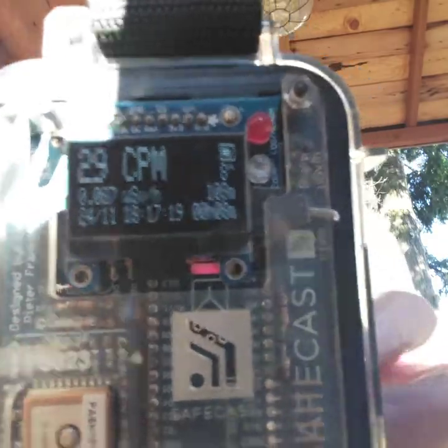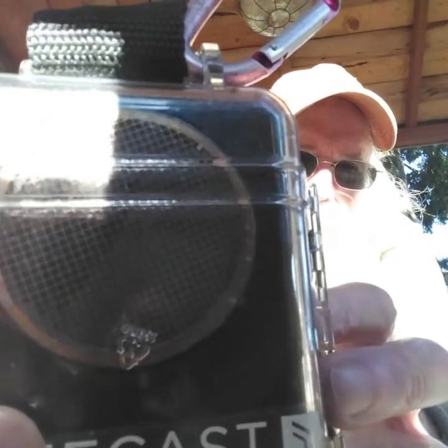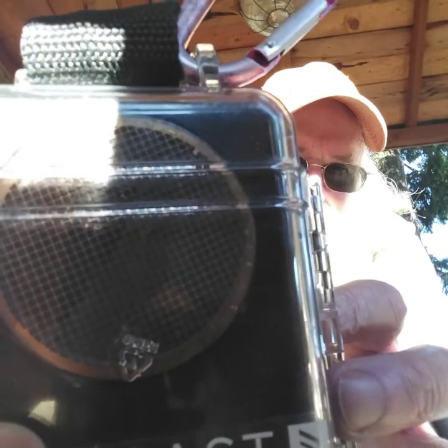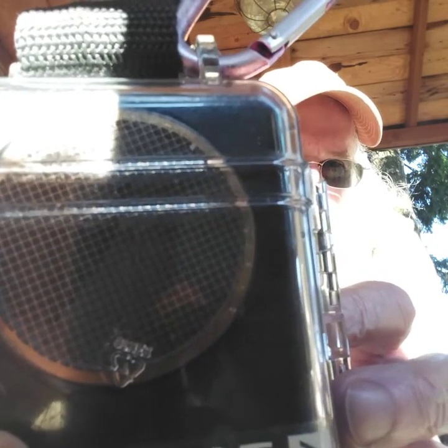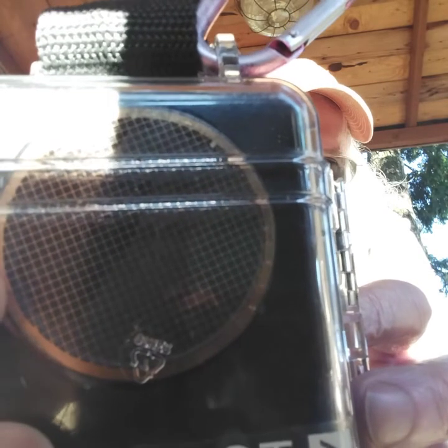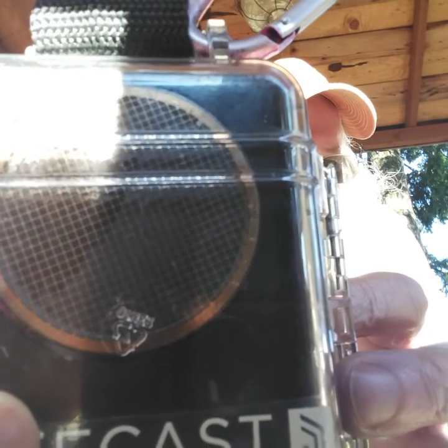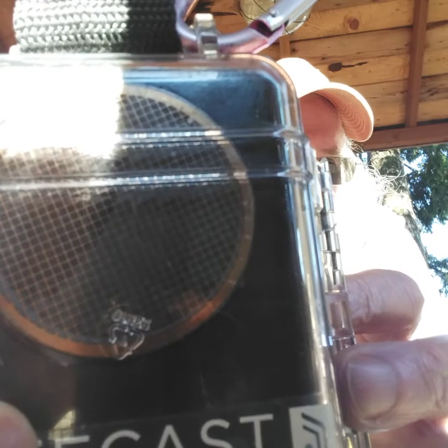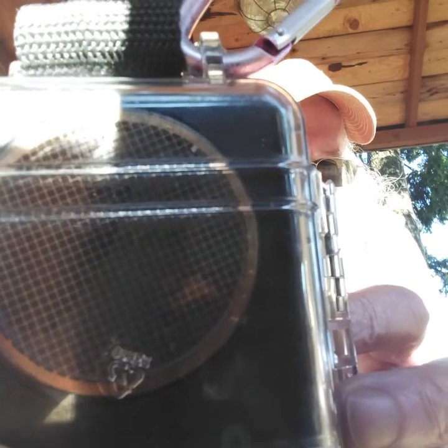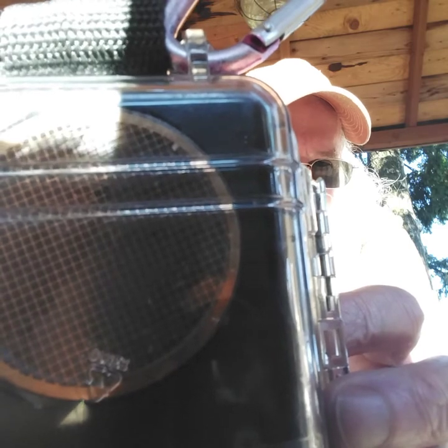So what is this? This is based purely on, can I get it to see it? This little round pancake tube. It's called a Geiger-Müller tube. It operates off of 500 volts. Very precise, temperature corrected and adjusted 500 volts. That 500 volts energizes a grid in there and makes the electrons ready to come off of that grid very easily. This Geiger-Müller detector can measure alpha, beta, and gamma energy. But I'm going to open that up a little bit further in a minute.